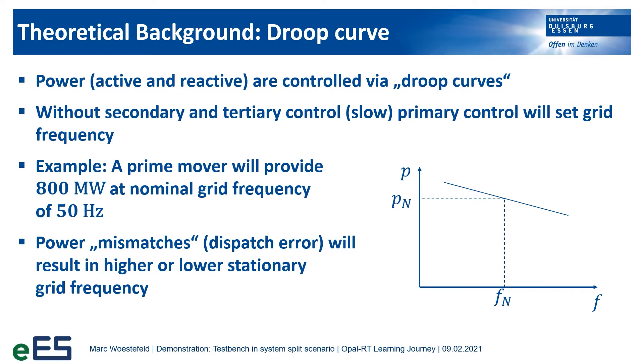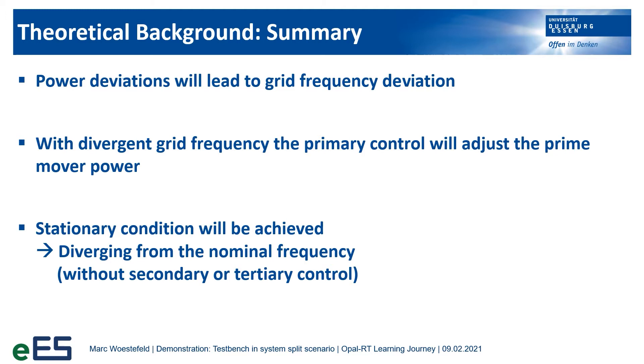When the frequency drops, it provides more power. Vice versa, when there is more power needed, it leads to a lower frequency. To summarize, power deviations will lead to grid frequency deviations, and grid frequency deviations will lead to an adjustment of the power in-feed from the prime mover. In the end, there will be a stationary grid frequency, but it will not be the nominal frequency without any additional control forms.